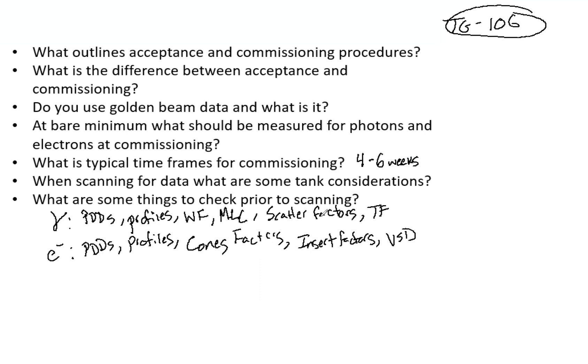For tank considerations when scanning for data, the tank needs to be at least 5 cm larger than your largest field size, and you'll want approximately a 75x75 cm cube tank. If your tank is too small, you won't achieve full scatter conditions, which will limit the accuracy of your results. You also want to use distilled water and watch for evaporation, which can happen overnight and throughout the day.